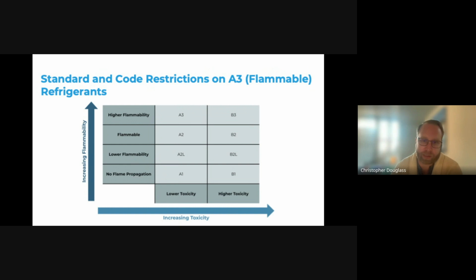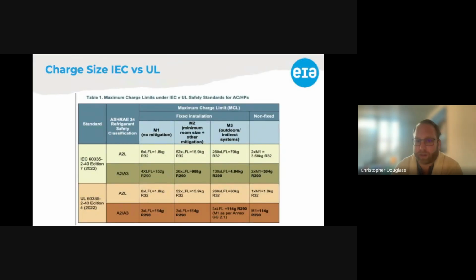If we go to the next slide, here we can compare how the global landscape looks with the IEC standards compared to the US and our domestic UL standards, in terms of the maximum charge size for flammable refrigerants, specifically A2 and A3 refrigerants.